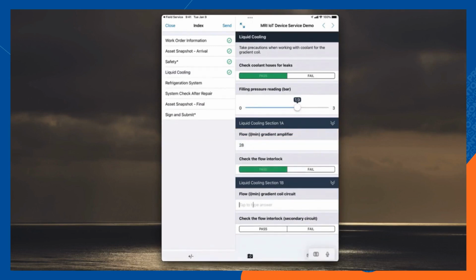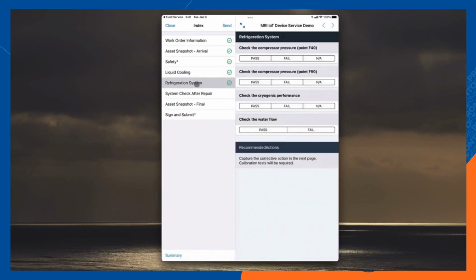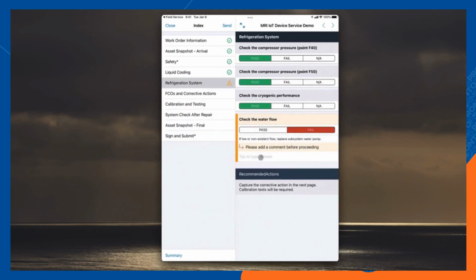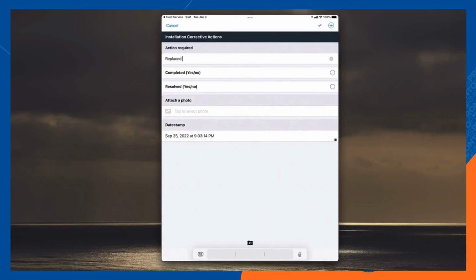I'll complete this section and move on to the refrigeration system. Everything looks good except the water flow rate. When flow is low, the prescribed action is to swap the water pump. I'm prompted to capture the corrective action and perform a few tests. I describe the action, indicating it's complete and the issue is resolved, adding an annotated picture of the part replaced.